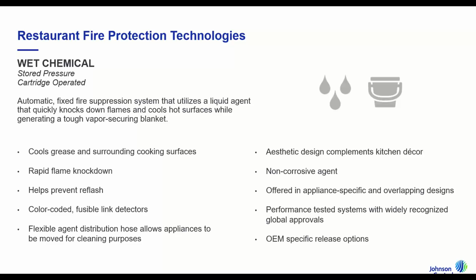manufacturer specific. And there's two different primary technologies with that, which would be a stored pressure type system or a cartridge operated system. Both of which have an automatic means of actuation, and they essentially trigger in the event of a fire event or a heat event, melting fusible link detection, or a manual actuation from a pull station. Upon system actuation, it's all or nothing, so the entire system would go off at the same time simultaneously, and it would knock out the fire instantaneously, while it's also creating saponification and the elimination of oxygen so that reflash does not occur.